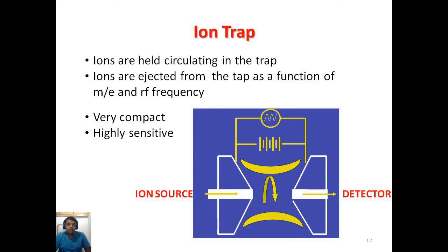Sometimes the molecules are fragmented properly, but on the way to the detector, in between the analyzers, they agglomerate or attach together, and do not provide the accurate molecular weight. Hence, these agglomerations are trapped by the ion trap, and finally only the molecules having their own m/z reach the detector.